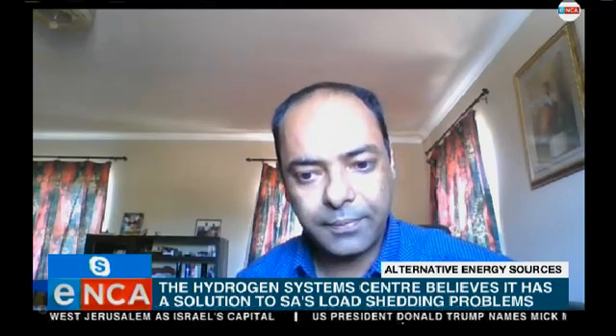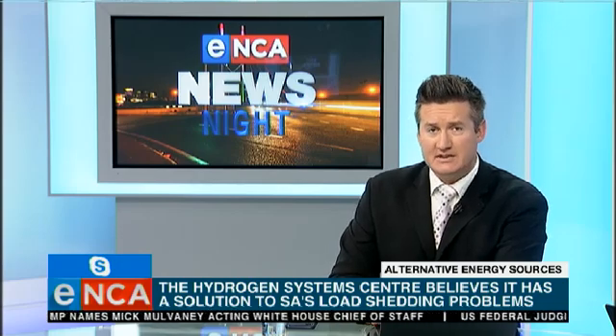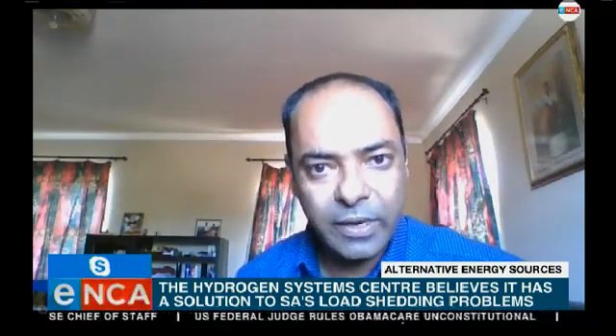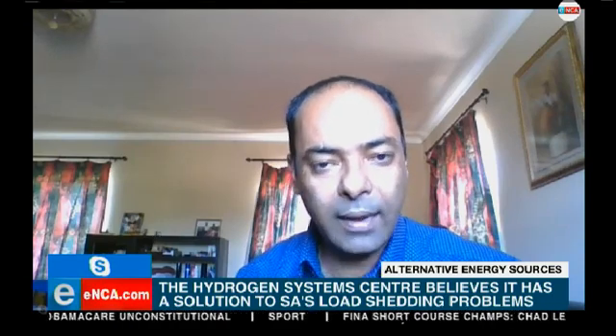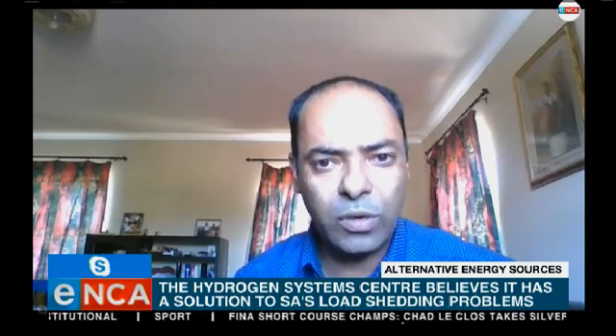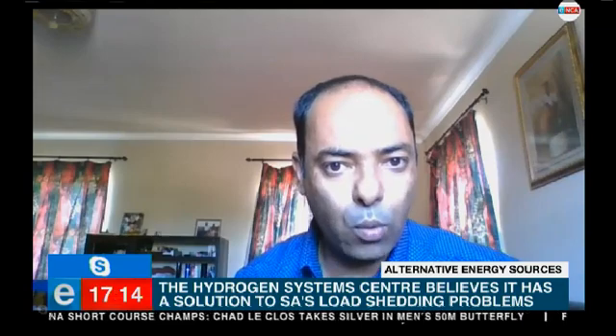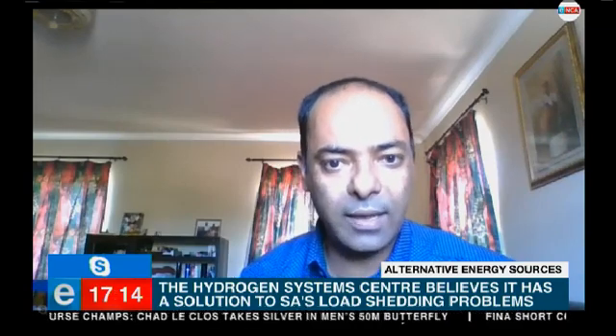What kind of energy output are you talking about? For somebody who doesn't understand engineering all that well, are we talking about being able to power a small household, a small suburb, maybe a shopping center? For a single household, we call it a combined heat and power system — a system which generates both electricity and heat, for the boiler and hot water needs of the family, and electricity for all the family needs. You typically need about one kilowatt of electrical power on average and about two kilowatts of thermal power. This unit can supply those needs.